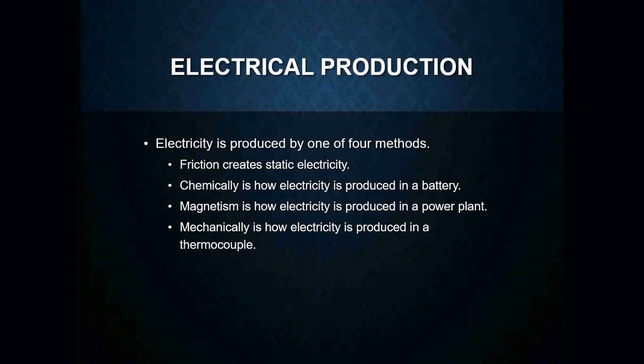Mechanically is how electricity is produced in a thermocouple. Thermocouples are really not found at all in oil heat, but you do find them in standing pilot gas furnaces. Basically, a thermocouple uses the flame from a pilot light to generate its own little millivolt circuit that will keep the pilot valve coil inside a gas valve energized so that the pilot valve will actually stay lit the entire time. This is an example of how we use heat to generate electricity to keep a device energized so that we can continue to light something.